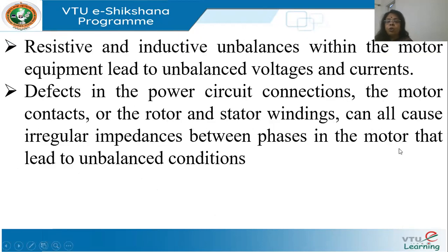Then when you have huge motors, like a 5000 HP motor or a 7000 HP motor, and if there is any unbalance in the windings, this can also lead to unbalanced voltages and currents. Defective distribution circuits within the facility of an industry can also lead to unbalance. Clear? With this discussion, you should see that voltage unbalances, of course, will lead to current unbalances, definitely. There are some causes from the load side and some causes from the utility side. Is there a cause of concern?